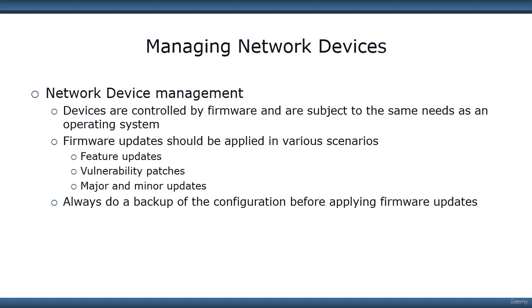You definitely want to read up on the firmware update and see exactly what it's doing to determine if it is something that's necessary. It's also a good idea to always do a backup of the configuration before applying firmware updates, because if we don't, then we can run into issues and a device not being able to be restored. Another key is power. Make sure you don't ever lose power to the device. So if you have a battery backup, you want to plug it in to that as well before you do any firmware updates.